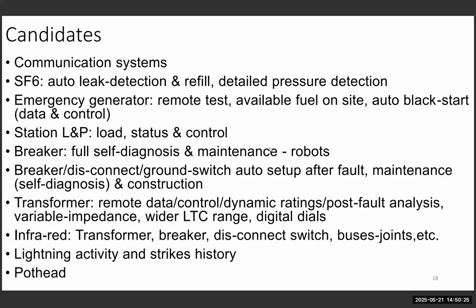Transformer, I mean, the one before that: anytime you have a failure, there are a lot of steps. The failure happens, the control room operator looks at the SCADA and makes sure the breaker is open, then sends an operator to the field. He or she needs to check the substation, make sure it's open, rack the breaker out, add all the safety tags, and then get the data for system protection. They don't access it remotely, so you have to download it. There are so many steps for something that happens pretty much every day. So in my opinion, if you have an intelligent substation, you have to automate a lot of this. Otherwise, it doesn't make any sense, because there's nothing really intelligent about it. It's just a very mundane task.